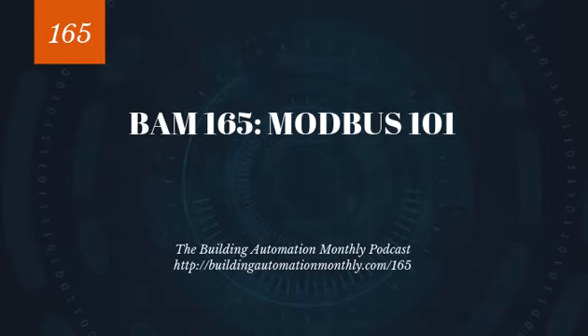Now, as I mentioned, discrete inputs and input registers support read functionality only. You can tell how important this is by the fact that I've repeated it about 4 times now. All right, now coils are single-bit objects that support read and write functionality, as are holding registers. Output registers also support read and write functionality, and they're 16-bit objects.